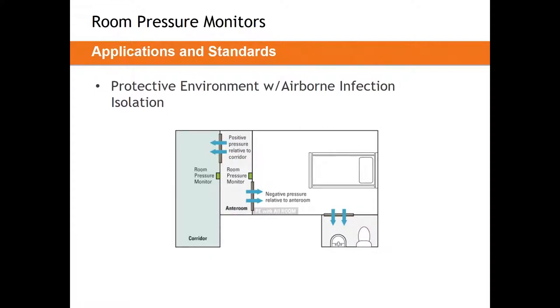You can get creative with these in that most digital pressure monitors can display multiple sensors on one screen, meaning you could locate the room pressure monitor only in the corridor while measuring pressure at two different interfaces. Most facilities will still go with two displays — one at each threshold — so you have a clear indicator as you pass through the interlocking doors.